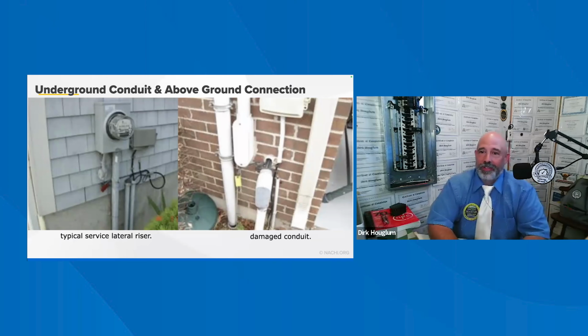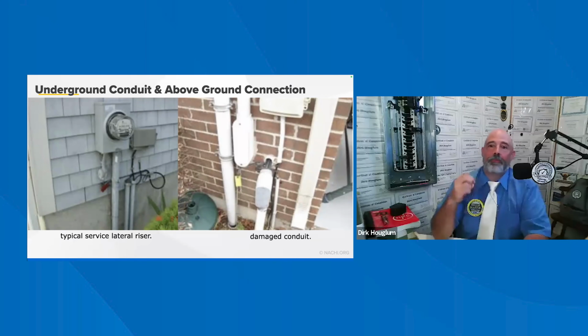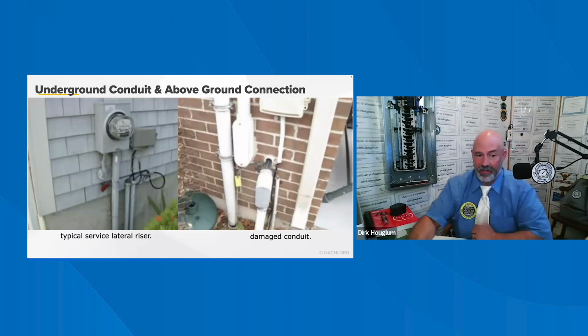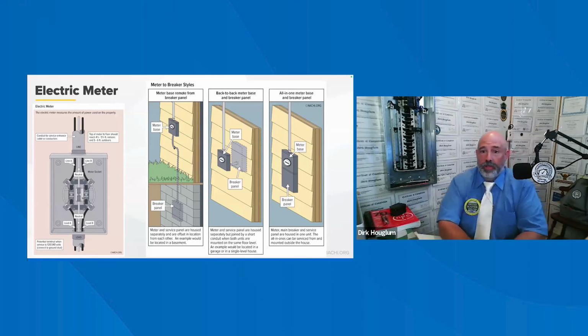Where the service entrance cable is not rated for direct burial, it needs to be in a full conduit and must be buried at a minimum depth of 18 inches under landscape and 24 inches under hardscape, such as driveways. In residential construction, there would be only one conduit. The home inspector should evaluate any visual signs, that is, above ground conduits, and report any damage or open joints that would allow moisture into that assembly. So pay close attention to that. I've seen quite a bit of that in my career. The electric meter here is not part of the service entrance equipment.